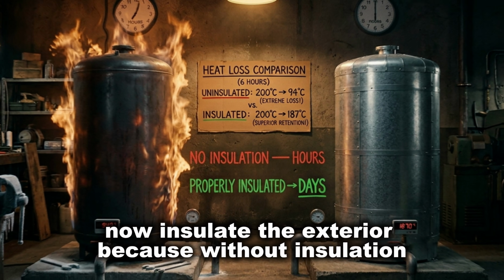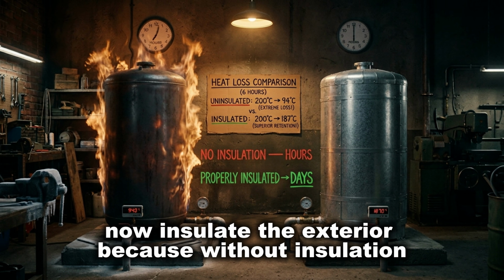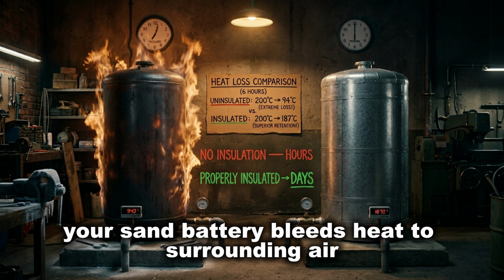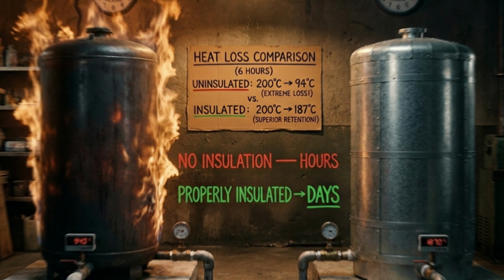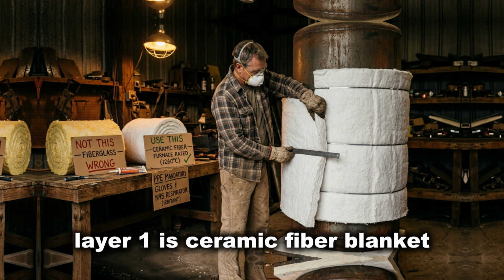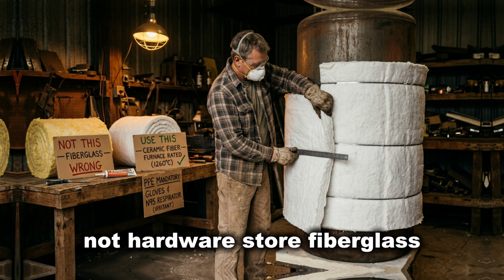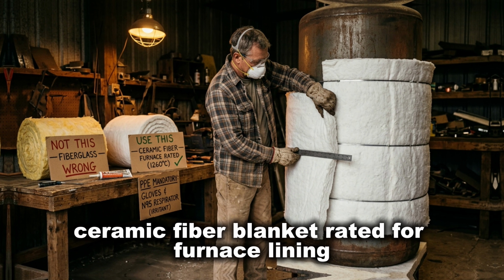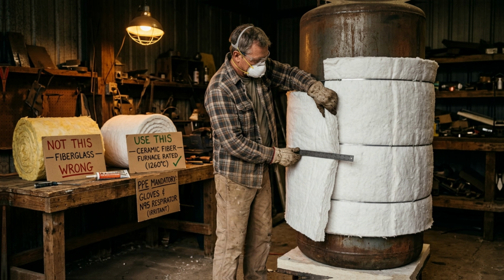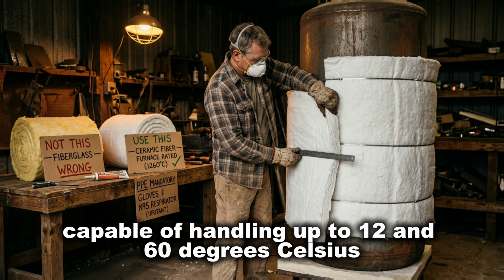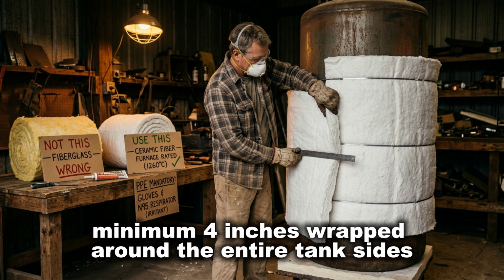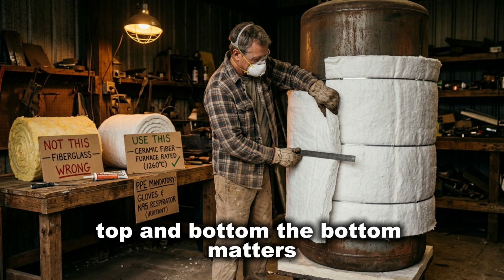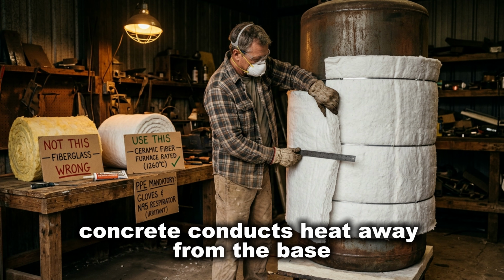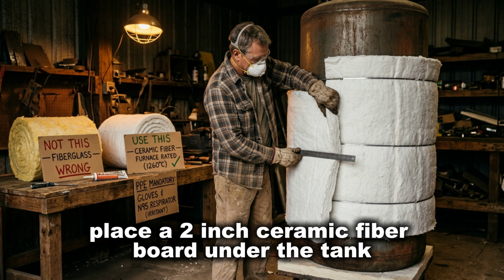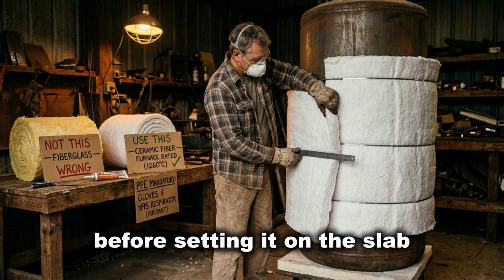or higher. Now insulate the exterior, because without insulation, your sand battery bleeds heat to surrounding air within hours instead of days. Layer 1 is ceramic fiber blanket. Not hardware store fiberglass, ceramic fiber blanket rated for furnace lining and industrial heat applications, capable of handling up to 1260 degrees Celsius. Minimum 4 inches wrapped around the entire tank, sides, top, and bottom. The bottom matters. Concrete conducts heat away from the base continuously. Place a 2-inch ceramic fiber board under the tank before setting it on the slab.